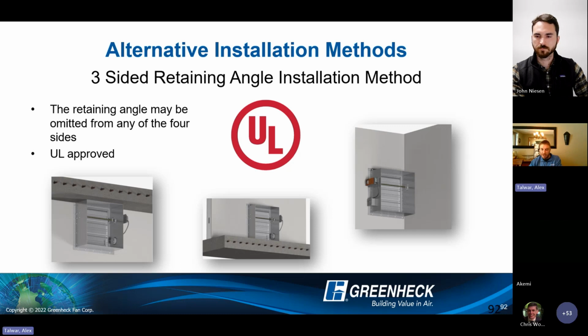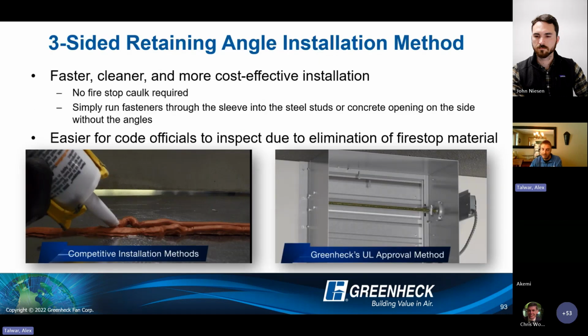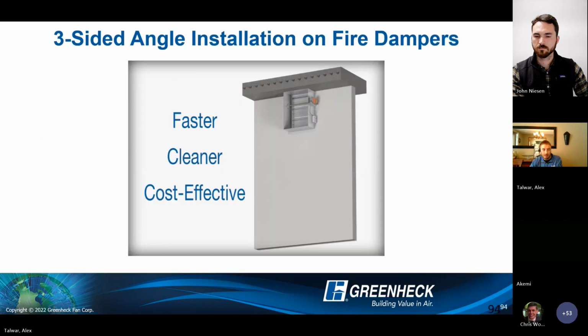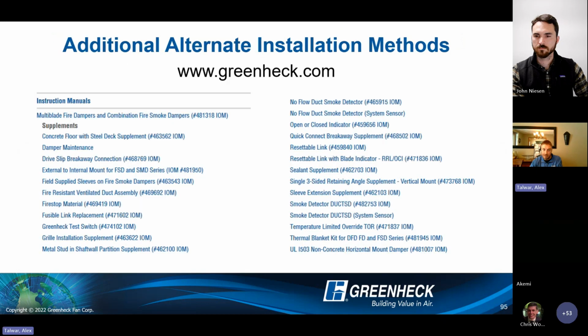A few get out of jail free cards that we kind of came up with. 3-sided retaining angle. If you have an obstruction in close proximity to one of your 4 sides, this allows install with a method with angles on 3 of the 4 sides and then fasten that 4th side directly to the opening. So that's kind of a handy get out of jail free card there. Really just a plug for all of our alternate installation methods.